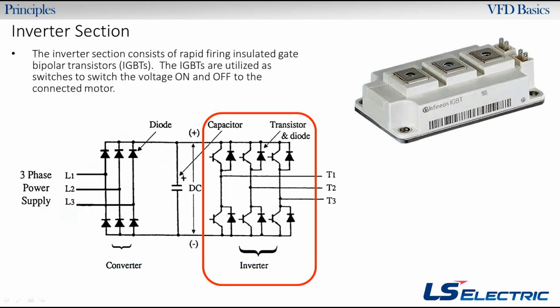So here's the last section, and it's probably one of the harder sections to understand, which is the inverter section. The inverter section is made of IGBTs. IGBTs are insulated gate bipolar transistors, a bit of a mouthful. But what they are is really just rapid firing transistors, and we're just using them as switches to turn voltage on and off going to the motor, okay?